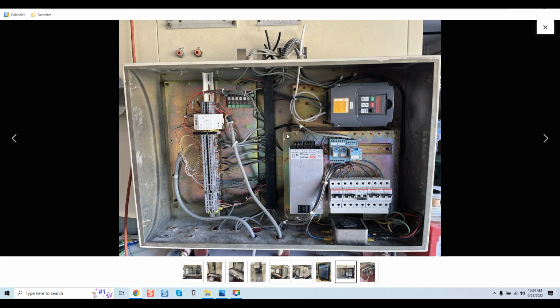This is the picture. I'm really grateful he uploaded this, because he obviously is not trying to hide anything. But in terms of showing it, I don't know if he's doing himself any justice, because seeing this and seeing what we see here, right down to wire pass-throughs not using the proper glands, this is ridiculous. Holes in the actual enclosure. I don't know what else to say. And we're not talking expensive parts here, guys. These are a couple bucks. You see a gland used right here, but nothing being used right here.